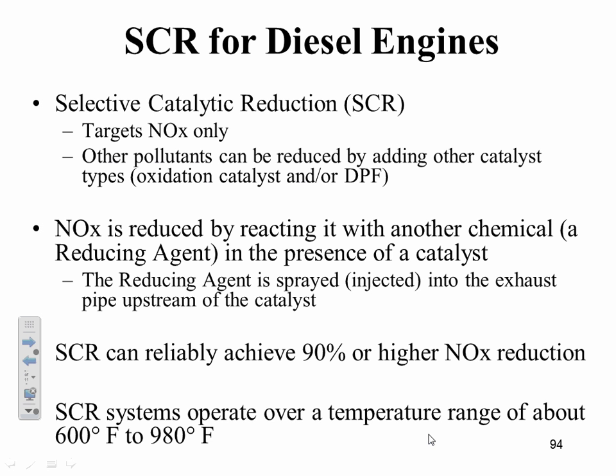The main thing, the SCR in this case is not a silicon-controlled rectifier like we in the electrical might think. It's selective catalytic reduction. This targets NOx only, the SCR does. And it's reduced by reacting it with another chemical, a reducing agent. Most commonly it's urea, a liquefied urea. And that can reliably achieve a 90% reduction in the NOx, but it's very expensive to add that stuff.